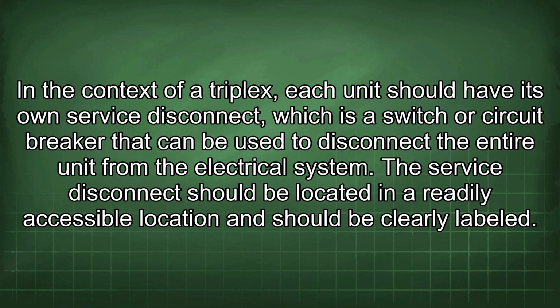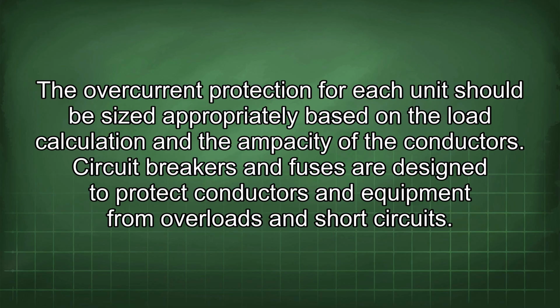In the context of a triplex, each unit should have its own service disconnect, which is a switch or circuit breaker that can be used to disconnect the entire unit from the electrical system. The service disconnect should be located in a readily accessible location and should be clearly labeled. The overcurrent protection for each unit should be sized appropriately based on the load calculation and the ampacity of the conductors. Circuit breakers and fuses are designed to protect conductors and equipment from overloads and short circuits.